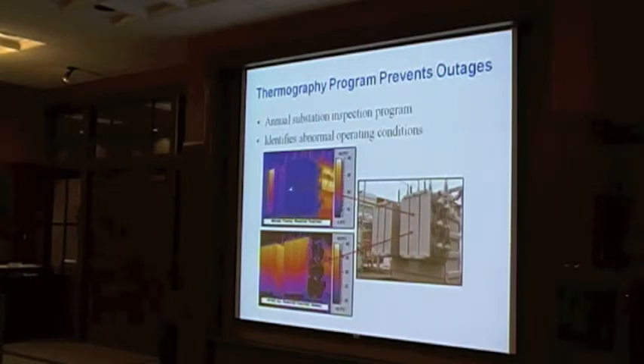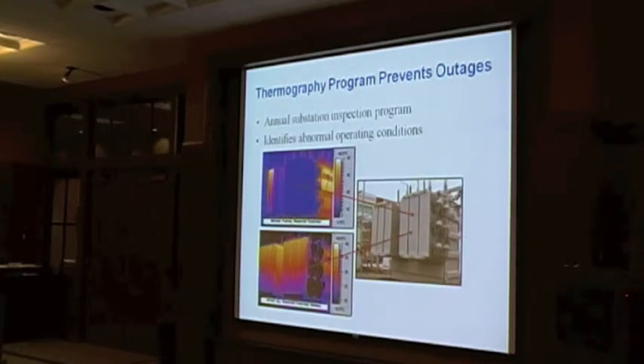And you can see right here in this picture, that fin should be hot, but it's cold. If it's cold, that means that oil is not moving about, and you can see this white level right there, that means the temperatures are quite high. Now, there are some safety devices built in. There's a high temperature alarm, and there's other alarms there, but if those were to fail, and this substation failed, that transformer is $700,000. So you don't want that. Those are high dollars, not only an outage. If the safety devices did work, we would still have an electrical outage.